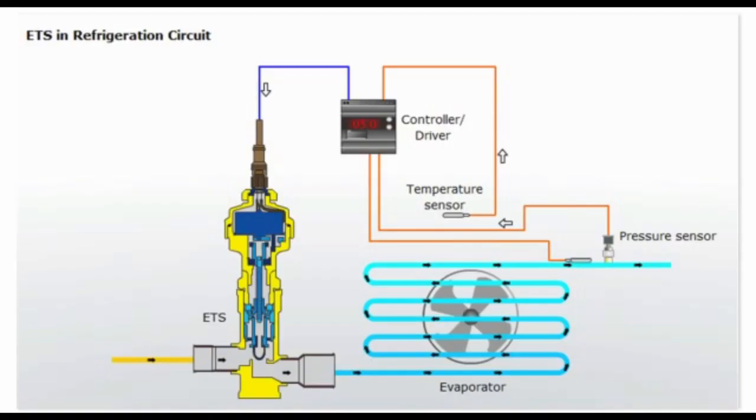The EEV allows for more precise control over refrigerant flow, which leads to better control over evaporator temperature and more efficient operation. By adjusting refrigerant flow to match actual cooling demand, the EEV helps reduce energy consumption, improve system performance, and extend equipment life. In the picture, it's shown how suction temperature and pressure are measured by the ECU unit, also known as EEV controller or driver, and its connection to the EEV valve.